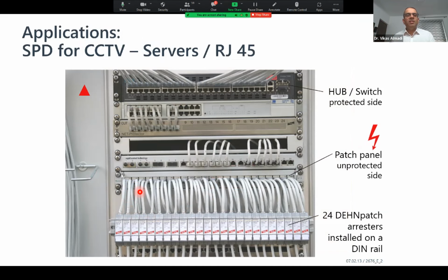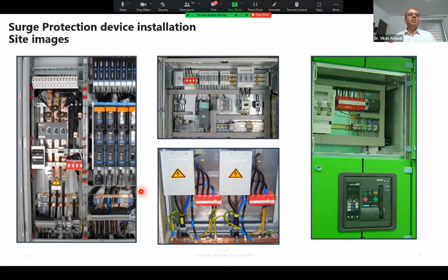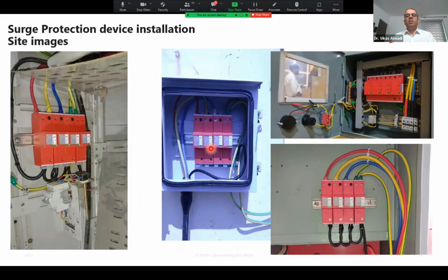So that there will naturally be some potential difference, but you have to neutralize it. You can't catch up with that voltage, or bring that voltage to zero. You have to bring yourself to that level so that the potential difference becomes zero. And these are some other applications in the panels where the SPDs are used to equalize at the entry level so that there is no disruption in the important services this power is catering to.